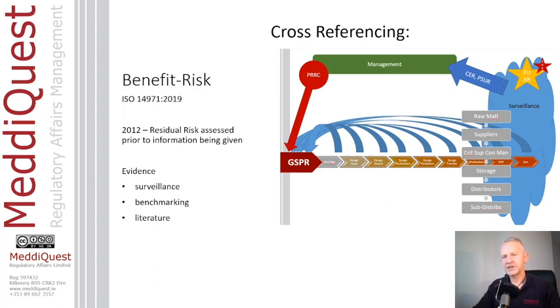And I mention this because putting those words the wrong way round has been known to give people a major non-compliance with pedantic notified bodies, because they claim that if you put them the wrong way round, you're following the old standard. So now we're going to have to say benefit-risk assessment, even if that isn't in our vocabulary as an organisation, if we've got one of these highly pedantic notified bodies who are more interested in process than the safety of the products. Okay, that's my little bit of a rant for today, so I've got that off my chest.